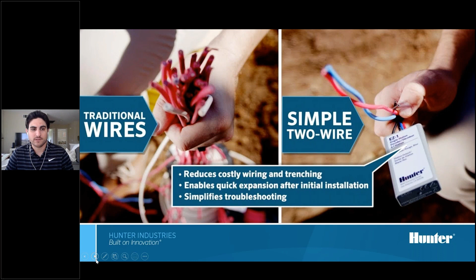So traditional two-wire systems at Hunter Industries would be the likes of our ACC, ACC2, or iCore, and our ICD and dual decoder system. A traditional two-wire decoder system, we've touched on this already, but the majority of the pros are you're saving a ton of time and labor, getting money back in your pocket by not having to run so much copper wire.